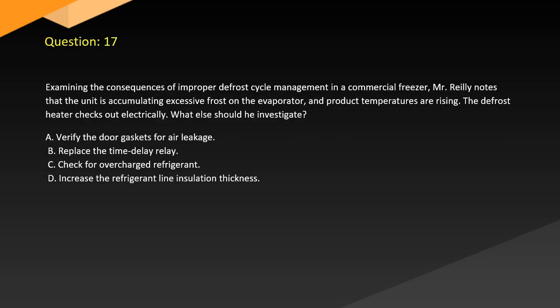Question 17. Examining the consequences of improper defrost cycle management in a commercial freezer. Mr. Riley notes that the unit is accumulating excessive frost on the evaporator and product temperatures are rising. The defrost heater checks out electrically. What else should he investigate? A. Verify the door gaskets for air leakage. B. Replace the time delay relay. C. Check for overcharged refrigerant. D. Increase the refrigerant line insulation thickness.